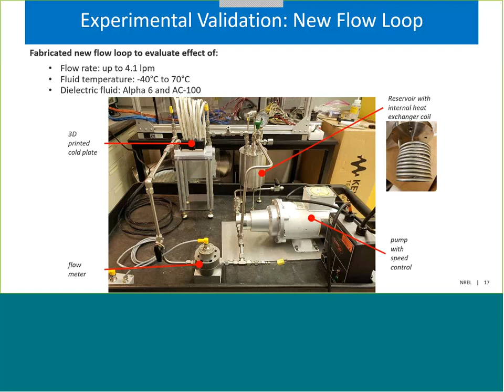And we're going to be looking at the effects of the flow rate. We want to conduct tests up to about 4 liters per minute. We'll probably take it a little bit higher than that, maybe 5 liters per minute, just to see the effects. We also want to look at the effect of fluid temperature. We want to look at temperatures from minus 40 degrees C, which can simulate a very cold winter condition somewhere, up to 70 degrees C. We're also going to be looking at different dielectric fluids. We're currently conducting tests with Alpha 6. We're also going to conduct tests with AC100, and we also plan to do tests with ATF as the coolant.